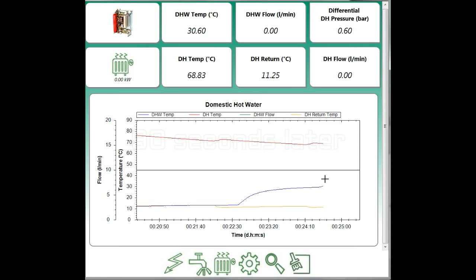Now we can see domestic hot water temperature has leveled off. And we can see the second pulsed input coming in now. So there's another little rise in domestic hot water temperature.